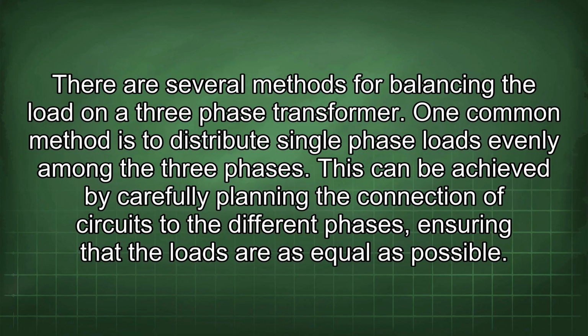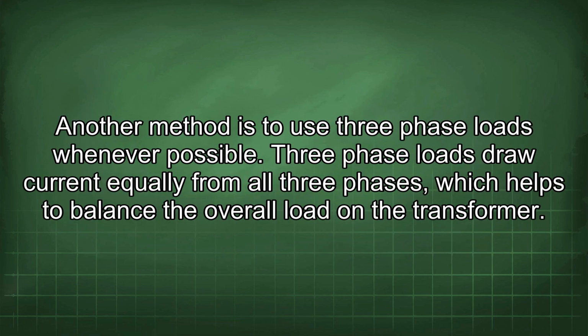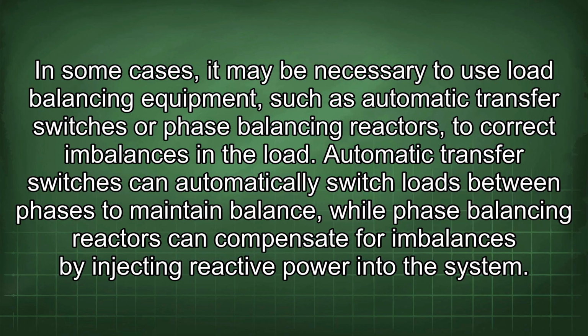There are several methods for balancing the load on a 3-phase transformer. One common method is to distribute single-phase loads evenly among the 3 phases. This can be achieved by carefully planning the connection of circuits to the different phases, ensuring that the loads are as equal as possible. Another method is to use 3-phase loads whenever possible. 3-phase loads draw current equally from all 3 phases, which helps to balance the overall load in the transformer. In some cases, it may be necessary to use load balancing equipment, such as automatic transfer switches or phase balancing reactors, to correct imbalances in the load. Automatic transfer switches can automatically switch loads between phases to maintain balance, while phase balancing reactors can compensate for imbalances by injecting reactive power into the system.